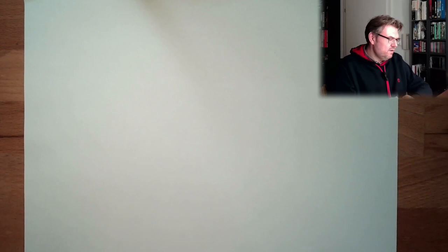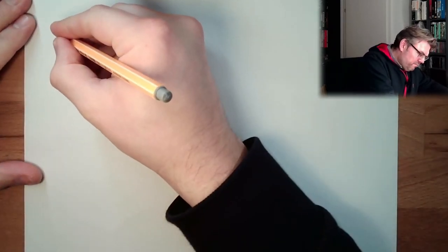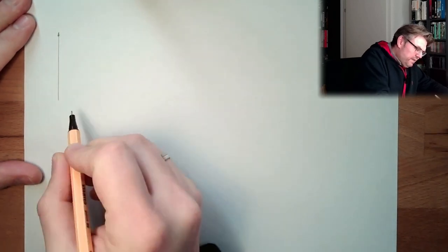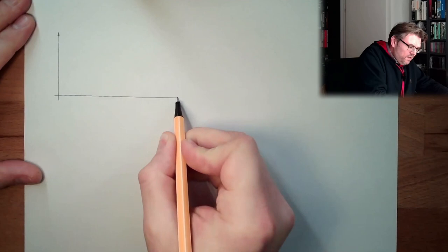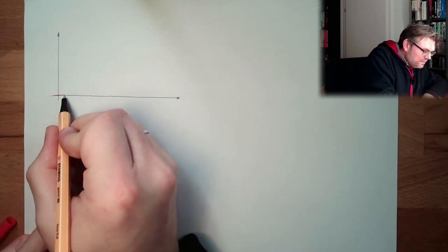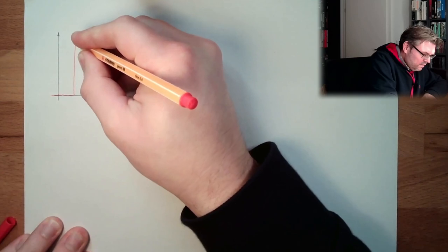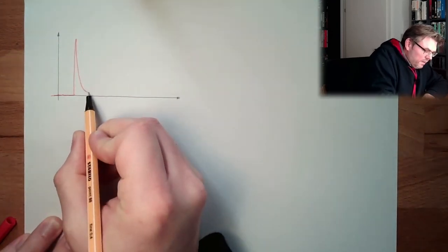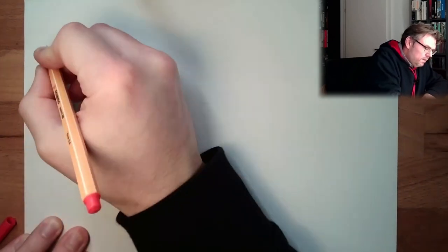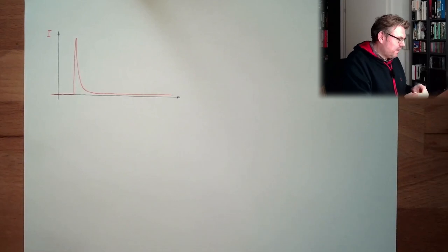Why are they getting stuck? I also did some research. I'm using LED lighting, of course, and now I realized LED lights are a capacitive load. It seems they behave like a capacitor. Even if the total power of this LED lighting is not that severe, every time I turn on, it's like charging a capacitor. So at this point in time we have a high peak, then it drops and stays pretty low. This is the current over time.